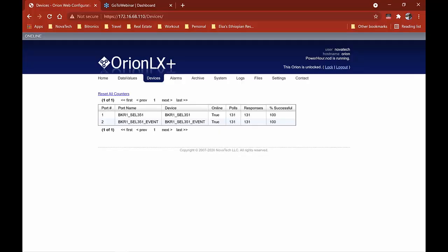The second port is only created so that he can trigger an event in the background. So this is only for testing purposes. Is that correct, EOB? Correct. So in a normal application, you don't need the second port at all. The events will happen on their own. Yep. This is more of a testing environment, since my Orion and my SEL 351 are off the net, aren't in a real application, we're doing 2 ports to generate that event on the second port.